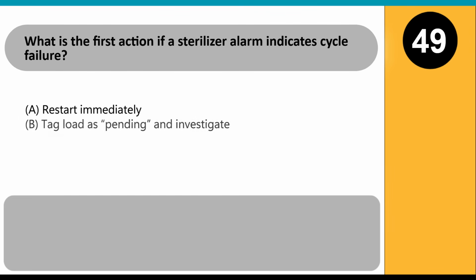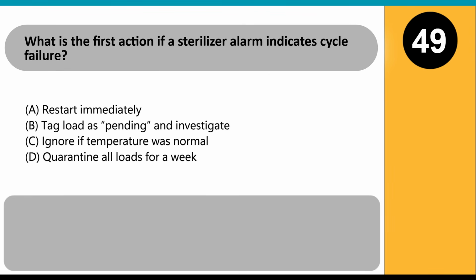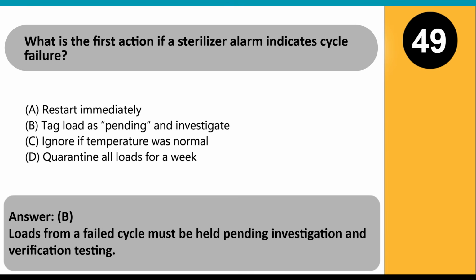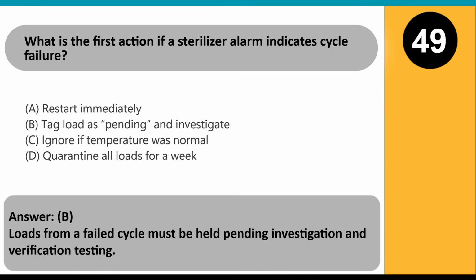What is the first action if a sterilizer alarm indicates cycle failure? A. Restart immediately. B. Tag load as pending and investigate. C. Ignore if temperature was normal. D. Quarantine all loads for a week. Answer: B. Loads from a failed cycle must be held pending investigation and verification testing.